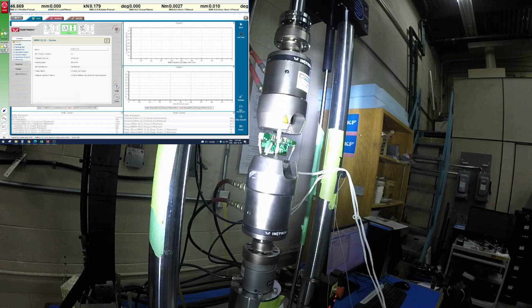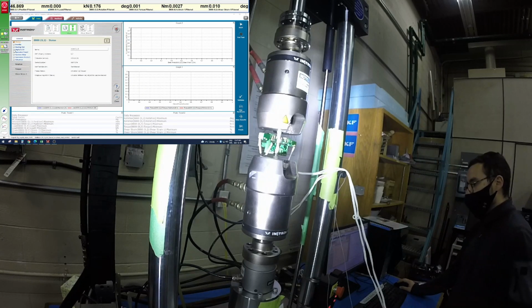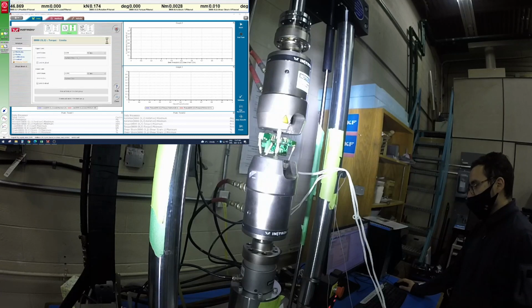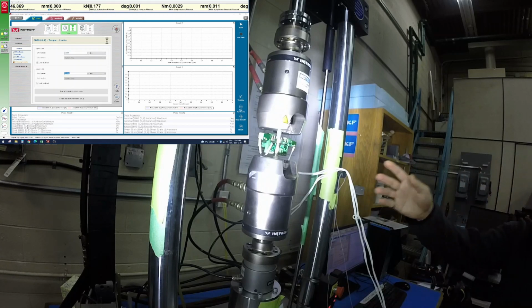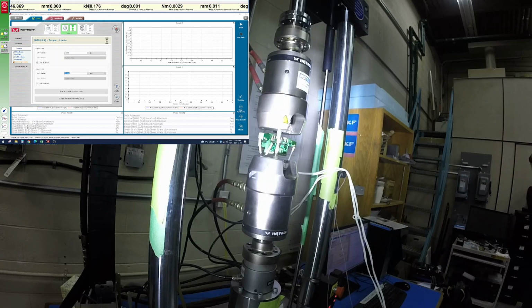And similarly, we can do the same thing for the rotation, the torque. So for torque, let's say we want 2 Newton meters and negative 2 Newton meters. For this particular material, that's what we know from previous specimens, what we would expect. But in general, a hand calculation will support you to figure out what these limits should be for the very first test, based on things like the yield strength and maybe a percentage of that with some safety factor.